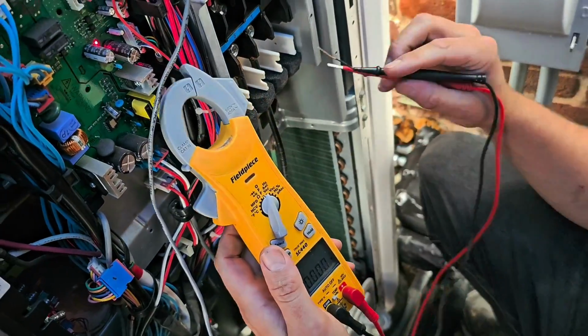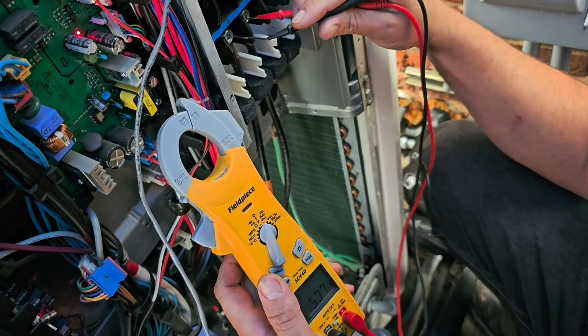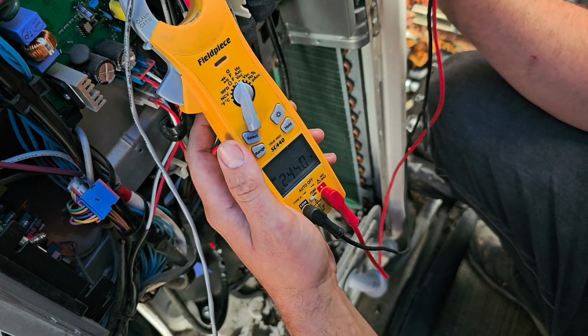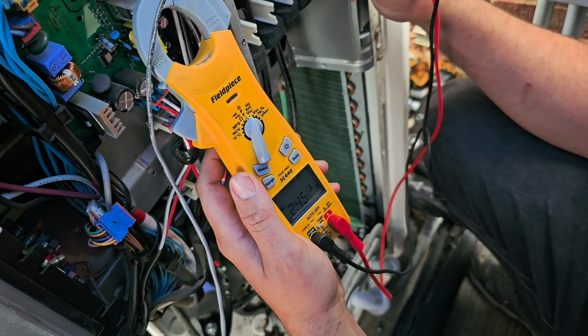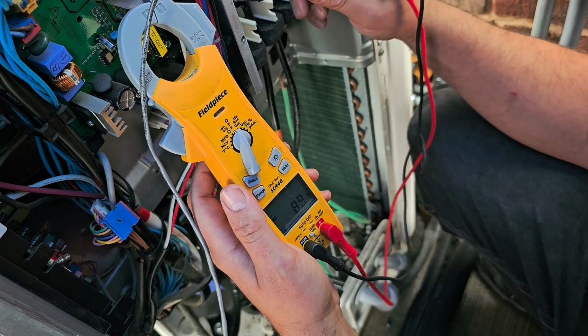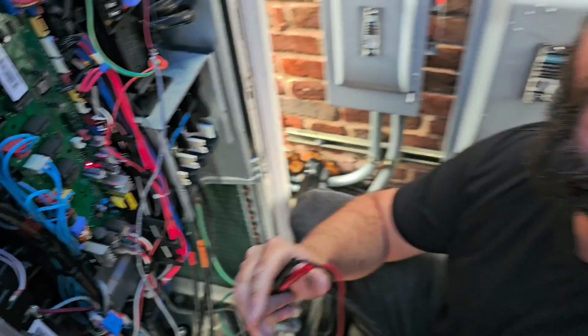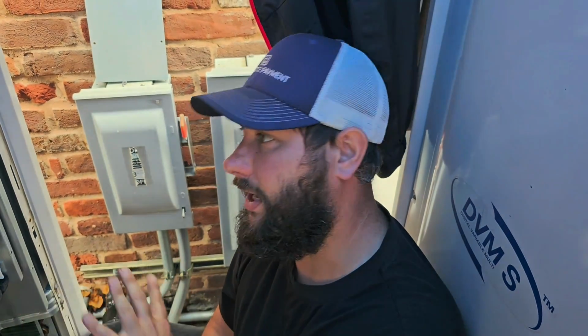So I put my meter on volts AC, and I went from T to S, and you can see from that phase to that phase we got 245, and then T to R 249, and then S to R 246. I wanted to make sure that I had every phase coming into the unit to make sure that I had the proper amount of power. That may throw another code, but it's just something. I start from the beginning. I start with the basics. So I check the power coming in to make sure everything is there.